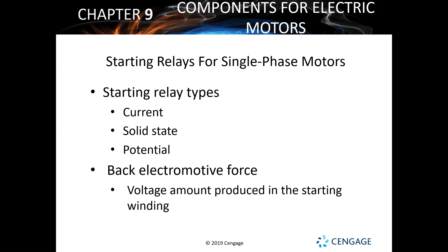So, like I said, a couple of different styles of starting relay types we've got: current, solid state, potential. The main thing is voltage is going to be the amount produced in the start winding. Back electromotive force, we're talking about voltage amount produced in the start winding. So how much energy is going to be needed right at that startup? That's what it's needing. That's that back electromotive force. Remember, electromotive force, that's just a fancy way to say voltage. So back voltage is the amount produced in the start winding. It's going to be that really high level of energy that's required when it starts up.